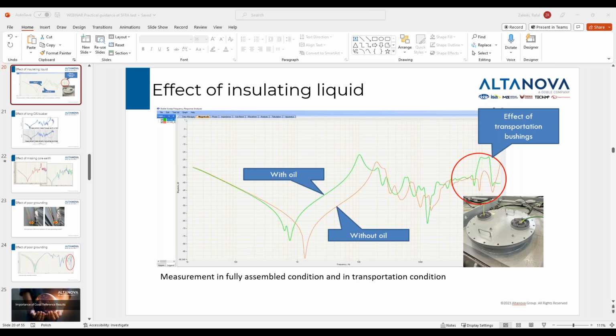Is it necessary to do the SFRA under routine tests on a transformer? Yes, of course. This is a question of your procedures, of your policy, how you want to test your transformers. And as I said before, the more tests you have, the easier it is later in future to pick up something from the past. At least SFRA should be done, in my opinion, once in a lifetime after the last installation, so that you have a good reference for your future tests. If it's moved to another place, I would suggest doing it again, especially as you will test this transformer anyway, and there is someone needed to test the transformer, so why not include SFRA? Whether in routine tests, that's a question of your time and money you want to spend.